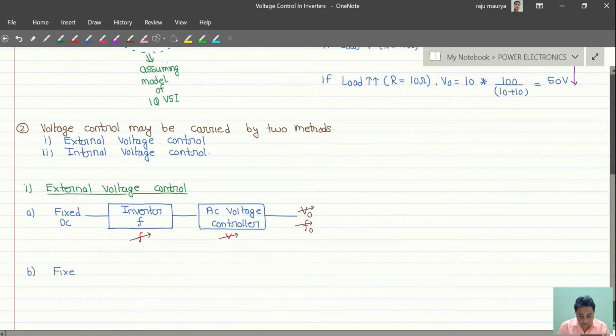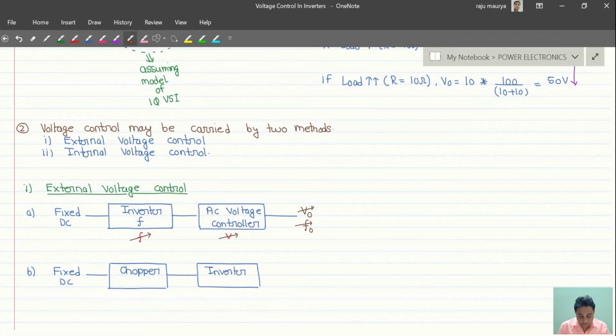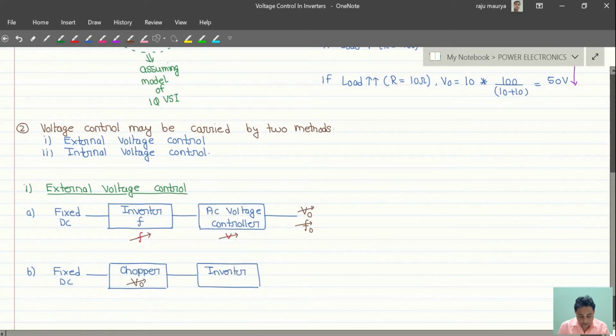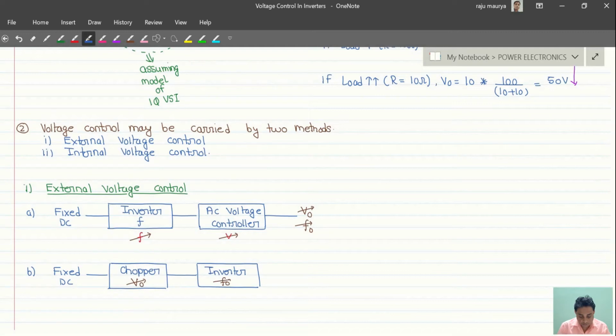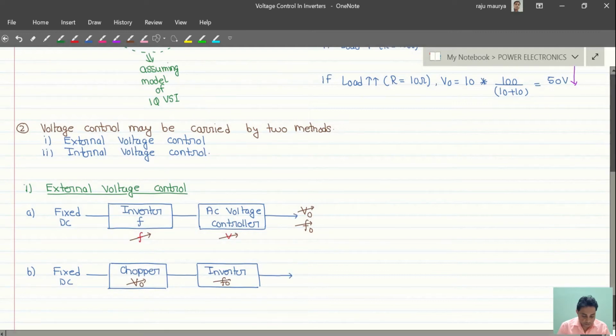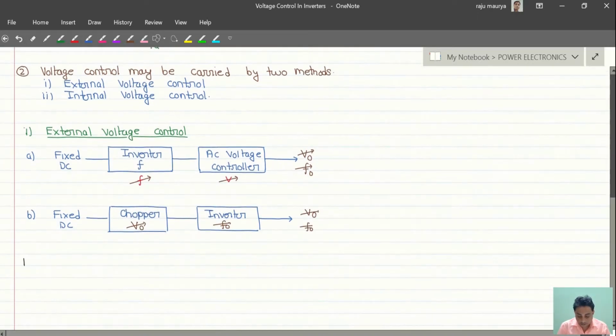In the second method, first we feed to a chopper circuit and then feed to the inverter. In the chopper circuit we get variable voltage, in the inverter we get variable frequency, and at the end we get variable voltage and variable frequency. Now, disadvantages or drawbacks of this method.